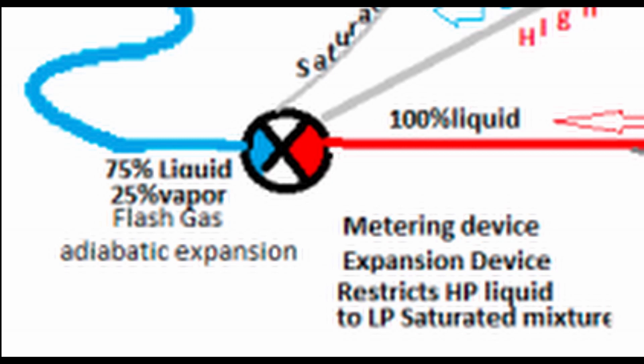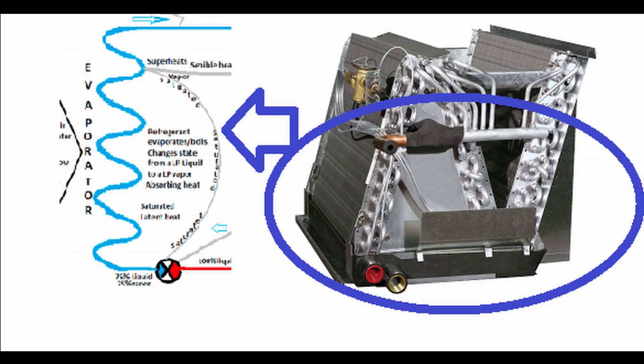That 25% vapor is called flash gas, also called adiabatic expansion. What's happening is that liquid is immediately flashing — changing state from a liquid to a vapor — absorbing heat from itself and from the remaining liquid, dropping that refrigerant's temperature so we're ready to start boiling. Now we have our evaporator coil: inside the majority of it, the refrigerant is saturated and boiling, changing state from a liquid to a vapor, absorbing a massive amount of latent heat away from the air — cooling the air.